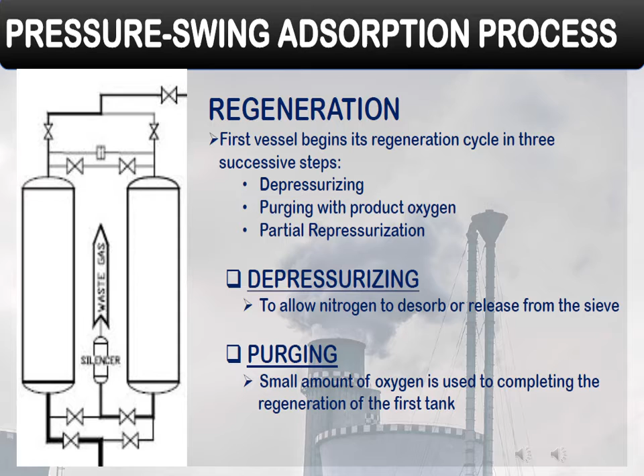The first vessel then begins its regeneration cycle, which is accomplished in three successive steps: depressurizing, purging with product oxygen, and partial repressurization, after which the vessel is again ready for the adsorption stage. Depressurizing allows nitrogen to release from the sieve, while purging uses a small amount of oxygen, completing the regeneration of the first tank. Partial repressurization is pressure equalization with void space gas from the other beds.